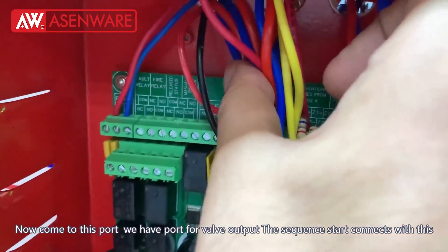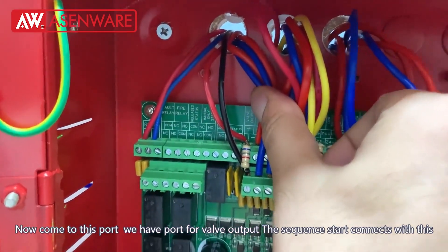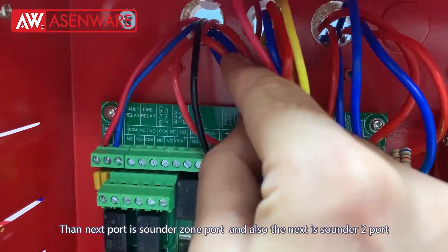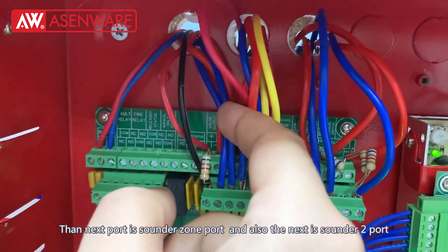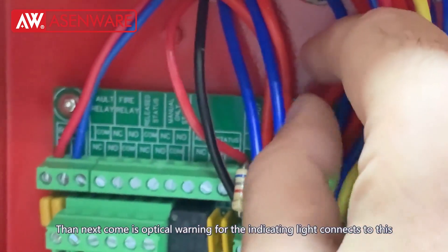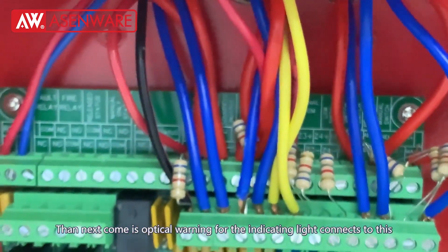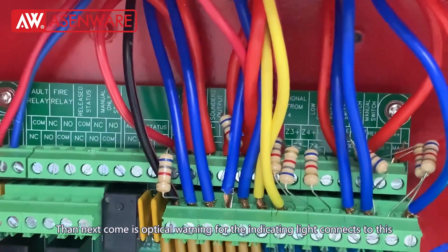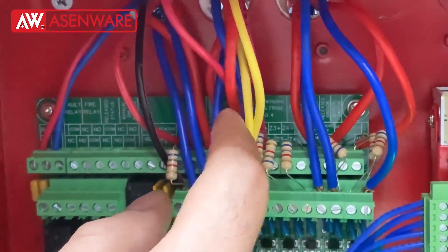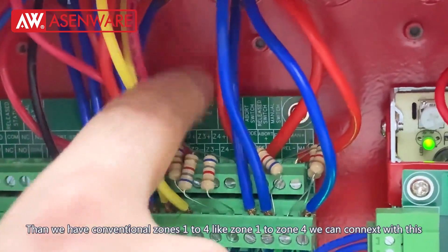Now for these ports: the first port we have is for the valve output — the sequence starter EM valve connection connects with this. The next port is sounder zone 1 port. Also the next is sounder 2 port. Then the next come is optical warning for the indicating light. Then we have AUX power 24V output. And then we have conventional zones 1 to 4 — zone 1 to zone 4 we can connect with this.